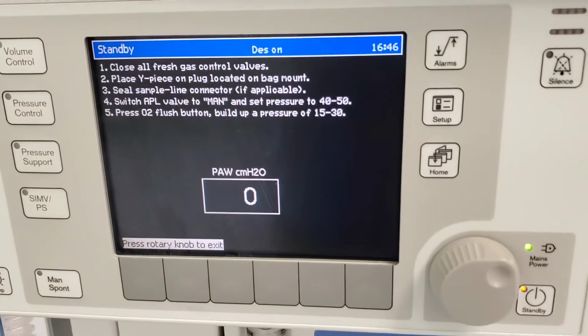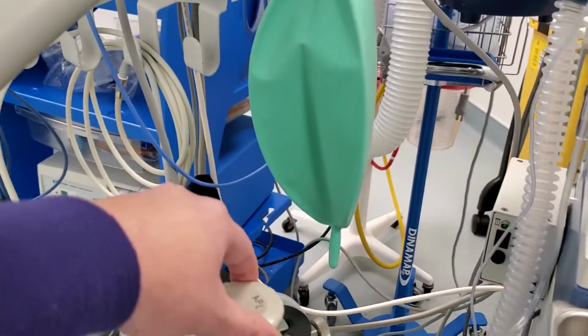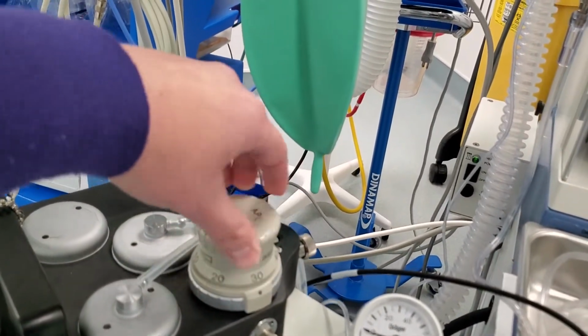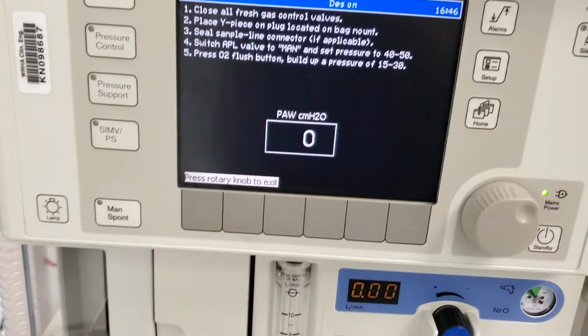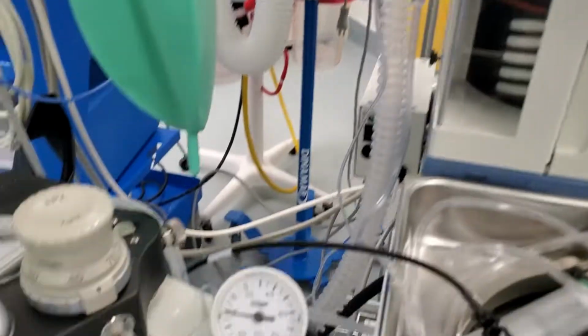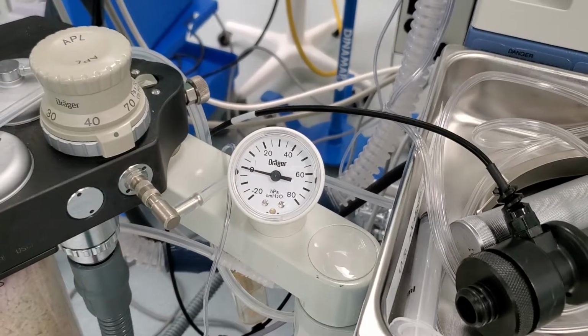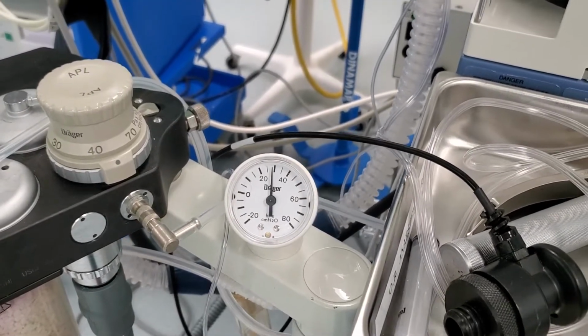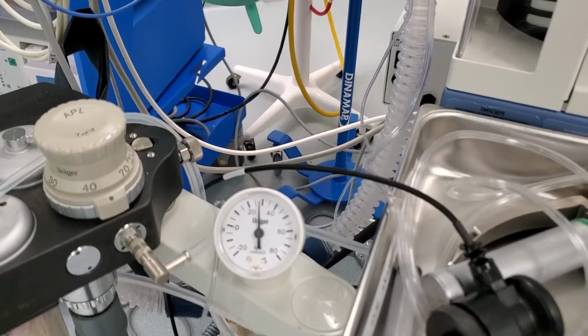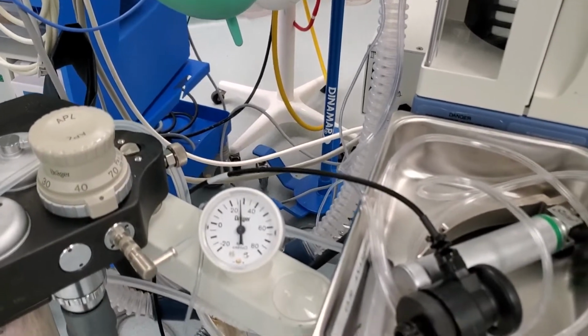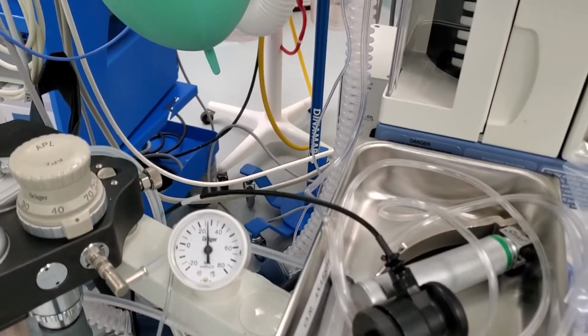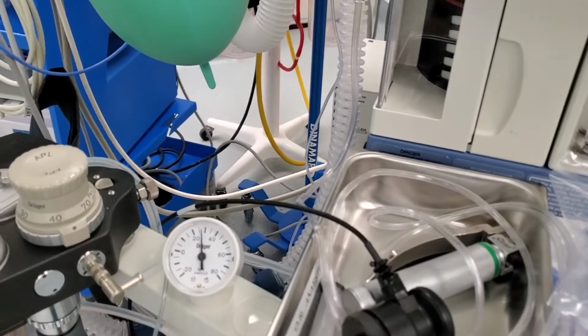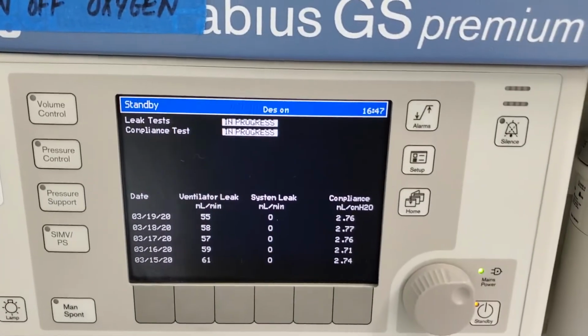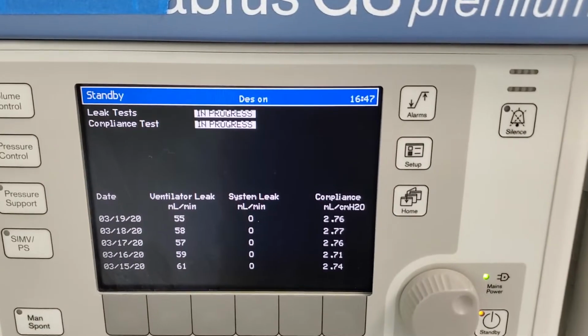As long as our anesthesia gas monitor is in standby, which it is, it will not interfere and cause a leak in the system. What we do is we then close the APL valve between 40 and 50, and then we push the O2 flush button, watching the screen or the pressure gauge to build up a pressure between 15 and 30 centimeters of water. If I was to go over, the high pressure safety relief valve would just vent open, and then I would have to do it again. So this test is now in progress. It takes a couple of minutes to complete.